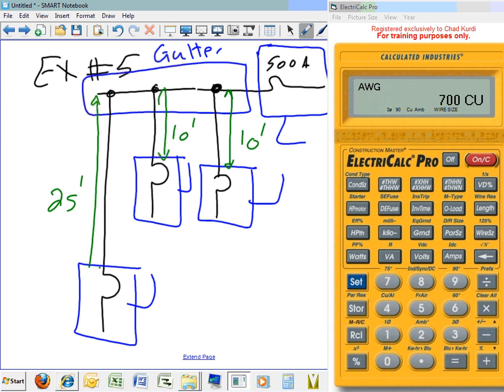But you can see, is there any circuit breaker from this point up to this point in this feeder, the 10 feet? No. Fuses? No. The next fuse is located right here for the feeder. Okay, so that's my tap. And this feeder, I will remind you, is a big feeder, a big conductor compared to the others. All right, so let's go size. There are rules for the tap. Rule number 1, these conductors have to have physical protection. You have to put them in a conduit.